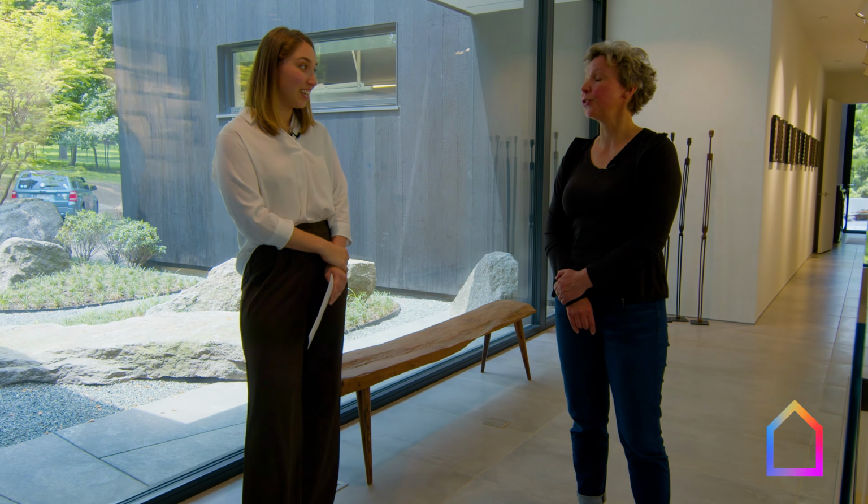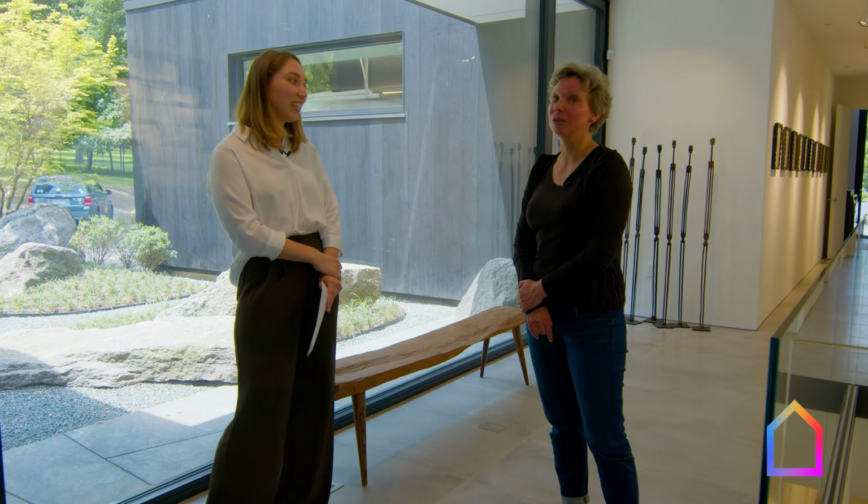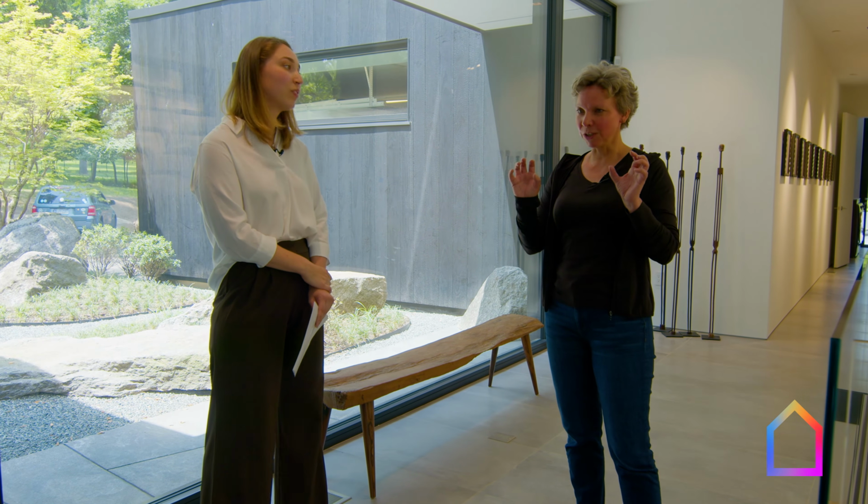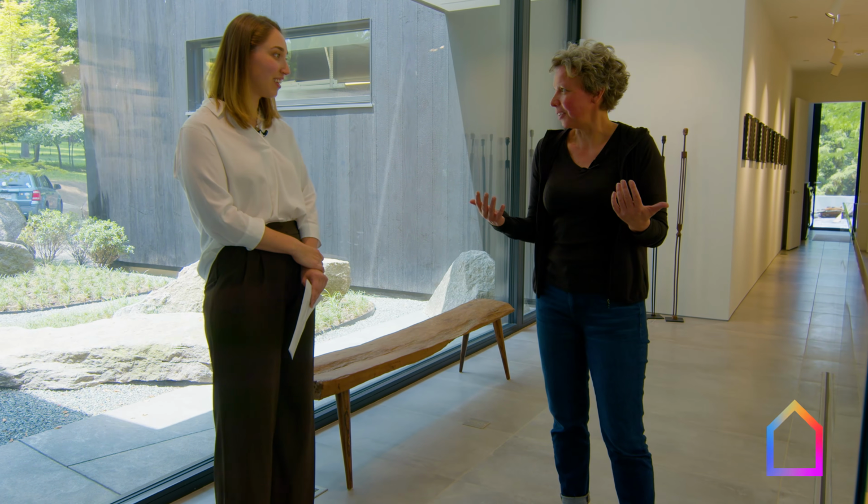Yeah, and it's great to have the right tools. The IR camera is really, really helpful. And the other thing is, you can only feel that draft if you really over or under pressurize the building. So it's something that typically you would never even feel.